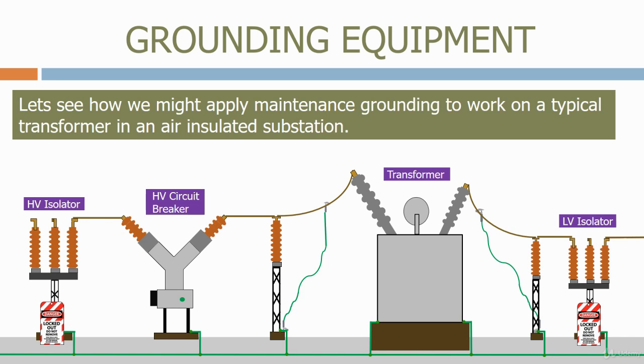again connecting the ground lead to the substation ground grid spigot before we connect it to the low voltage conductor. The transformer is now grounded on both sides, and a permit can be issued to work on the transformer.